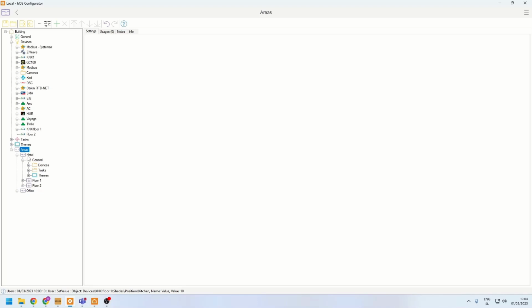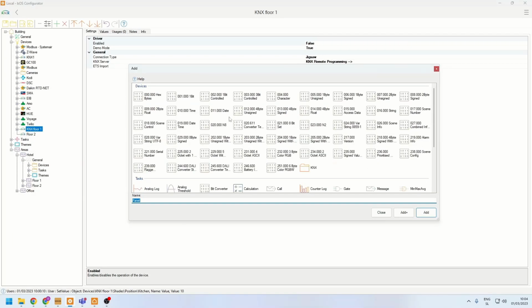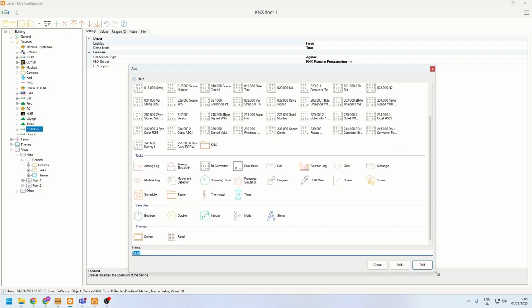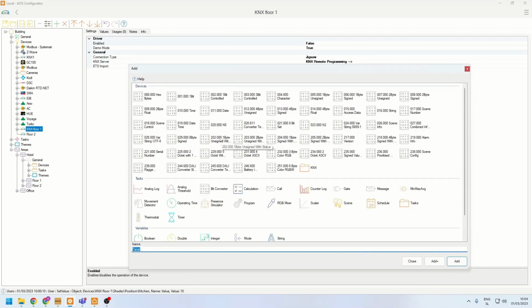Will it deal with a 6-byte object and split it into useful information? Yeah. So if I go to KNX here, I think there is a, let's see, a bit, 6-byte. I'll have to check, to be honest. 4-byte we have. 8-byte. Yeah, I think that you could use it here directly.